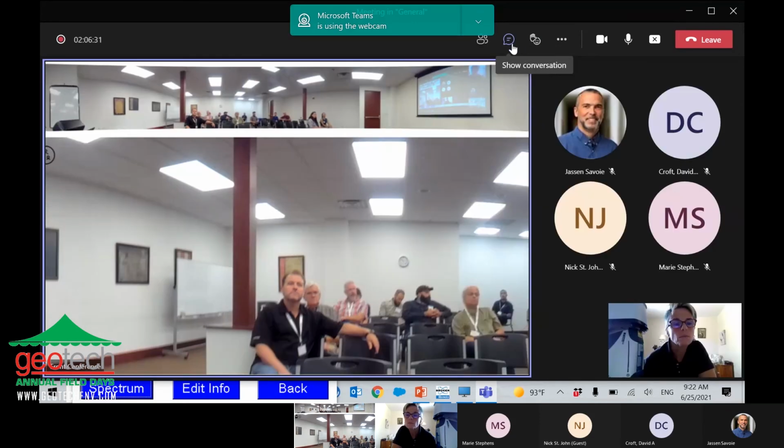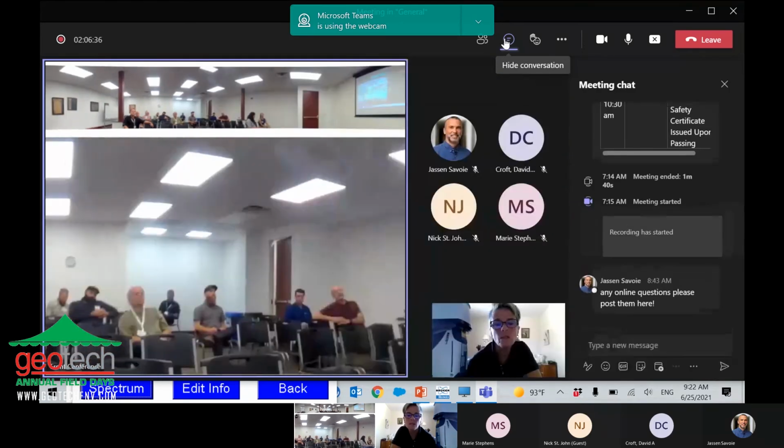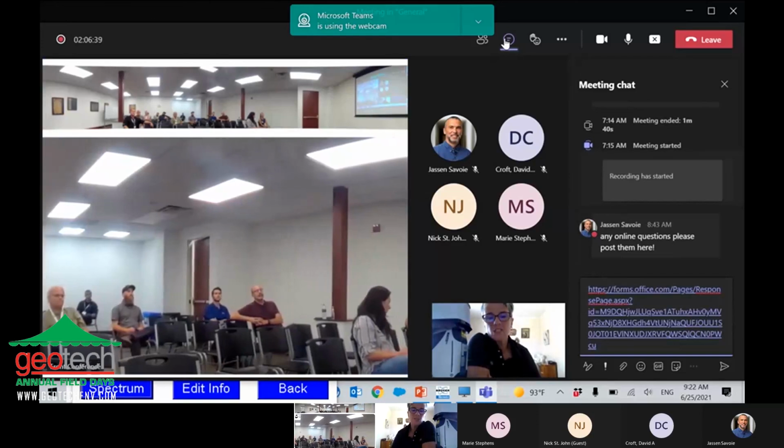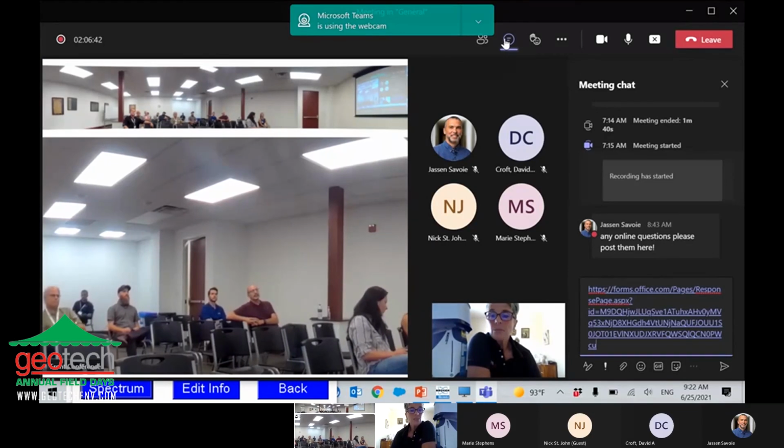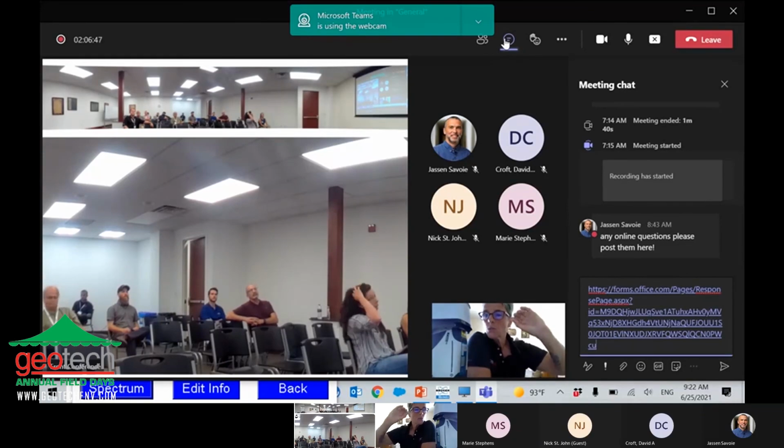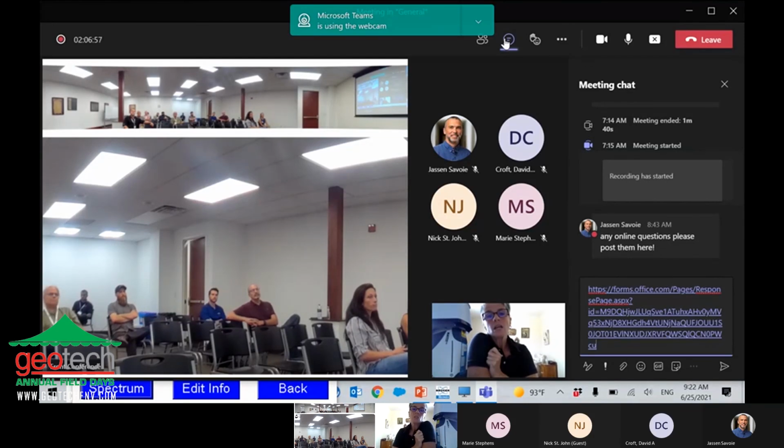I might have missed it, but what does LOD stand for? Limit of detection. That's the limit of detection for that element in that particular sample. What's nice is most XRFs show you what's detectable. They give you the elements that are detected with your error, and then they show you what elements are below the limit of detection, and what that element would have to be in that particular sample in order to be detected.